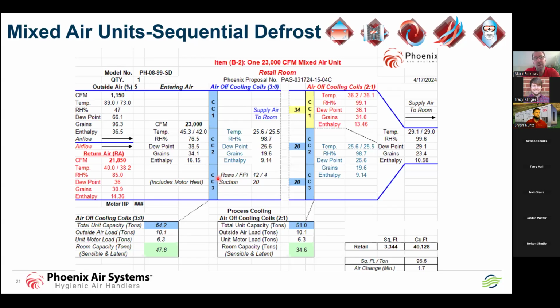The problem with all that is, number one, dampers are mechanical. They tend to fail if they're not taken care of. If one was to put hot gas through these coils, the end result is I'm going to have warm air on one of the coils converging with the cold air off the others. Therefore, we might have condensation problems. So what you're going to see on this, where you see the CC1 in yellow, we're going to intentionally defrost that coil on the fly.